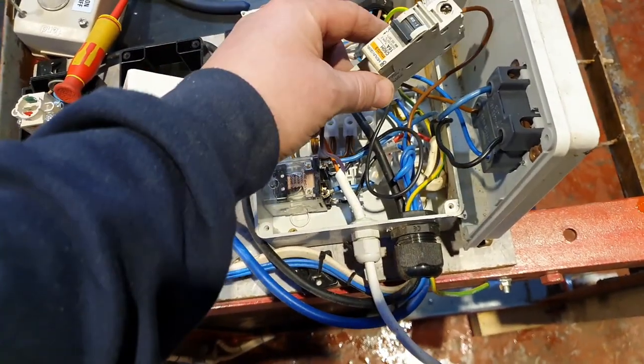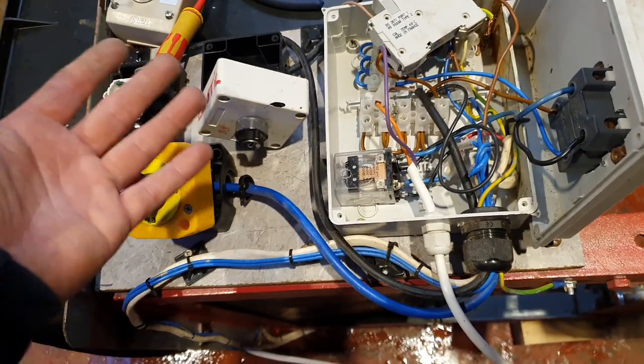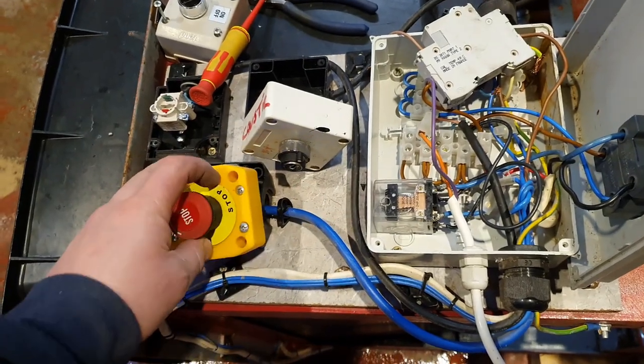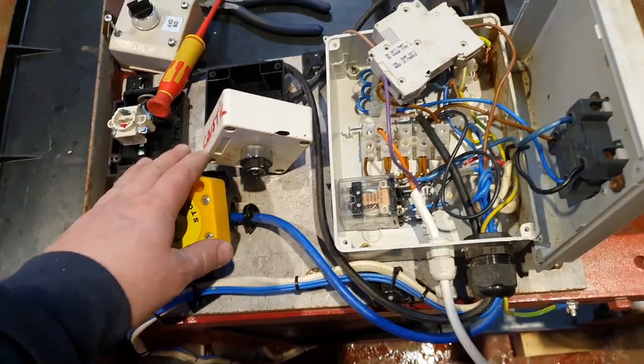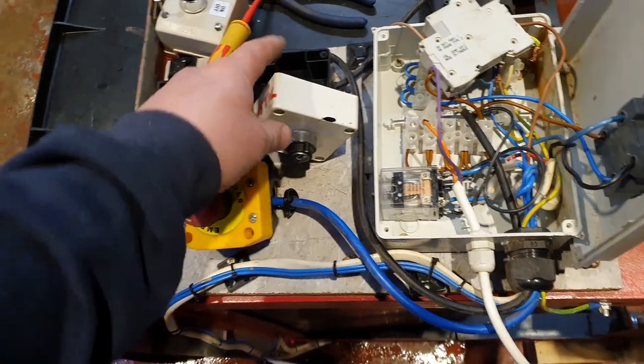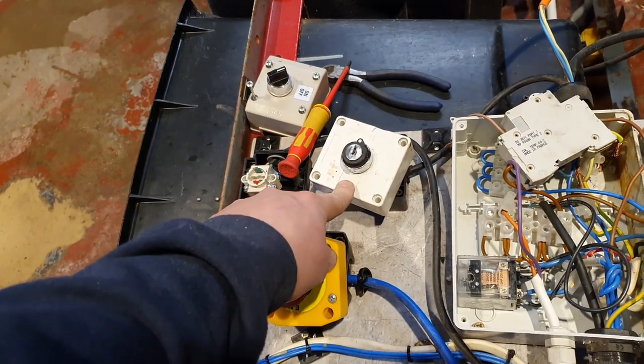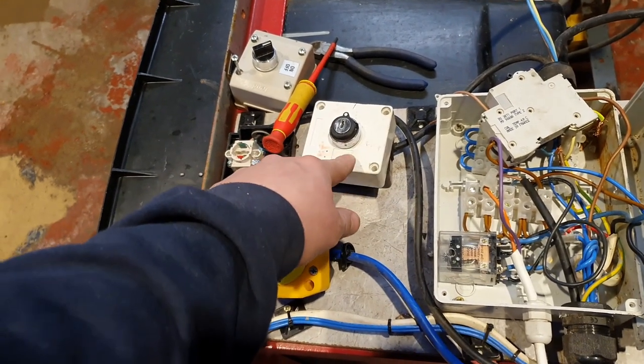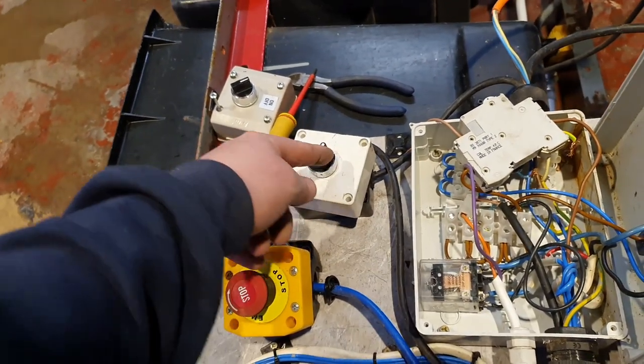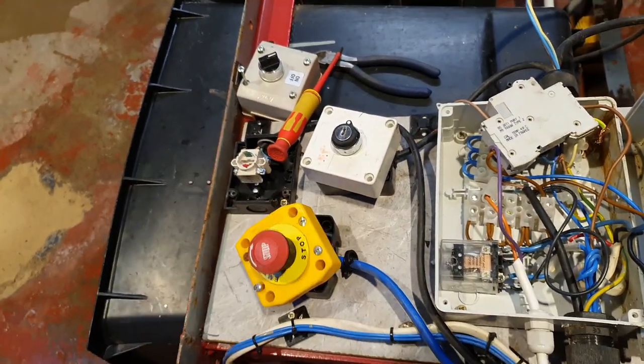This is just an overcurrent breaker - it's not actually an RCD, so there's actually no earth protection on this machine at all, apart from the main RCD on the fuse board which is a 300 milliamp type. I like to have things protected locally as well. Also, the drain for the rinse tank is right next to the pump start for the caustic, so very often you hit caustic by mistake and get a face full off the spray ball. And the emergency stop has stopped working.